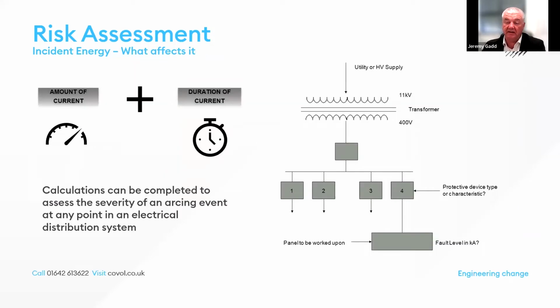So what affects incident energy? Well, incident energy is a combination of the amount of current and its duration. The diagram shows a very simple distribution system from the transformer to the sub-distribution boards. Protective devices which limit the amount of current resulting from a fault play a significant part when determining incident energy and understandably affect fault levels at sub-distribution levels. When assessing distribution systems for arc flash, incident energy values can be determined at any point in that electrical distribution system.